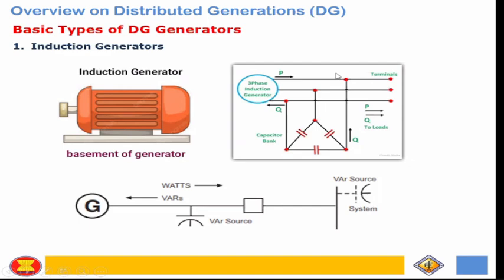Kasi when you are a DG, hindi ka po pwedeng kukuha ng VAR from the system. As much as possible, mag-produce ka ng VAR. Okay? While the induction generator has a kVAR requirement, it can be compensated by the capacitor. So when it's disconnected, yung induction generator, since mayroong capacitor dyan, it will cause overvoltage in the area. Okay? So mayroong mga ganyang scenario. And then it may cause ferroresonance as well.